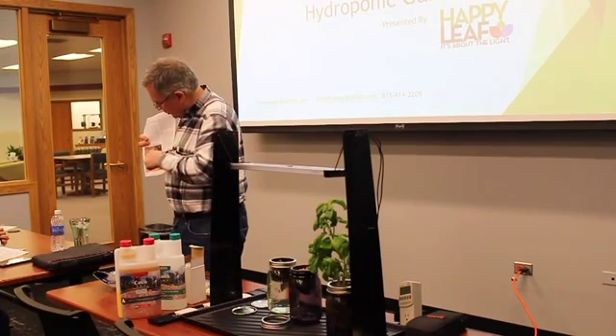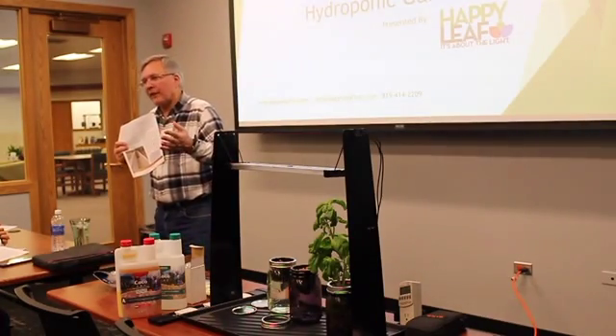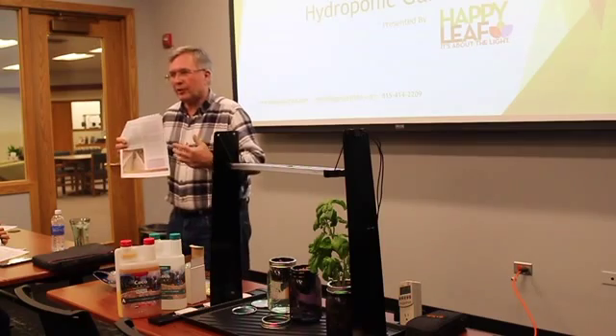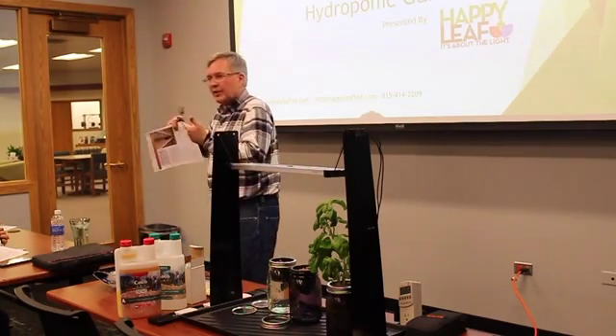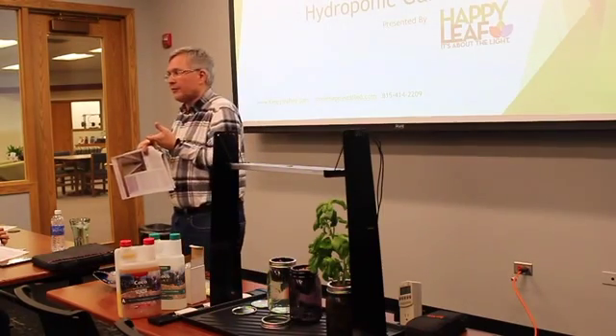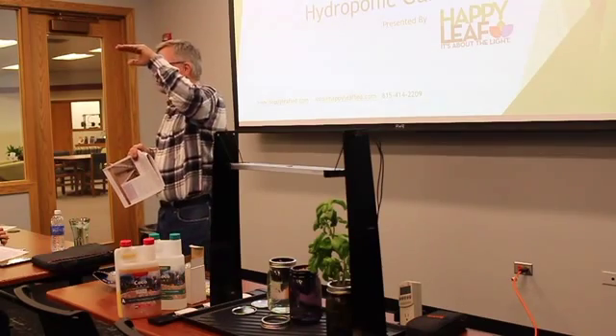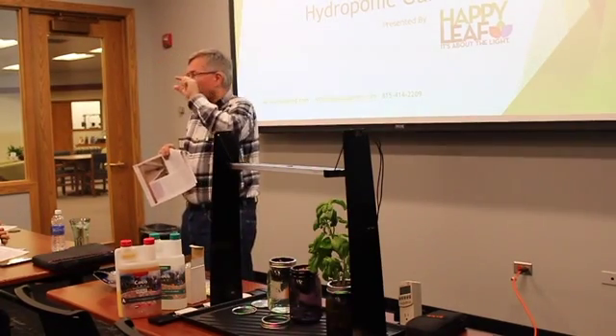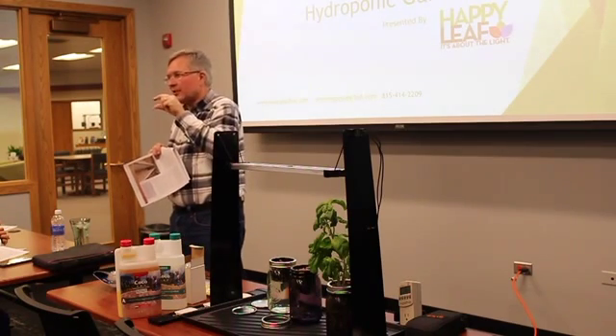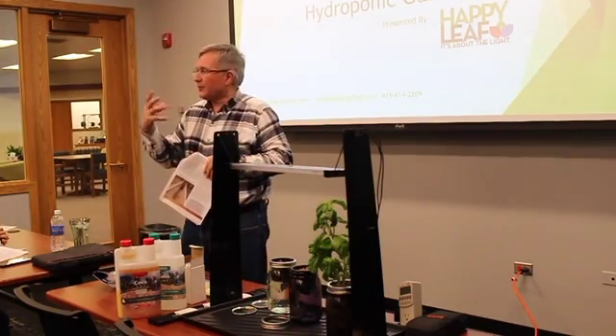By the time it goes through this room and into my heat recovery ventilator, that air is 45 to 50 degrees because of the earth. I've collected that energy from the earth in the winter, and then I run it through a heat recovery ventilator, which is a heat exchanger, and that exchanges the heat from the air that was in the bathrooms and the kitchen, and that air now is 55 degrees, and I only have to heat it up to about 70. So I only have to heat it up 15 degrees, even though it's 10 below zero outside. So it's sort of magical.